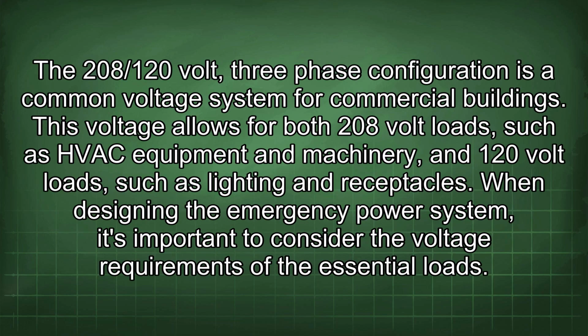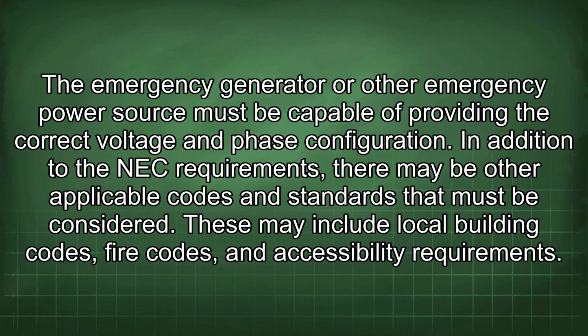The 208/120 volt, 3-phase configuration is a common voltage system for commercial buildings. This voltage allows for both 208 volt loads, such as HVAC equipment and machinery, and 120 volt loads, such as lighting and receptacles. When designing the emergency power system, it's important to consider the voltage requirements of the essential loads. The emergency generator or other emergency power source must be capable of providing the correct voltage and phase configuration.